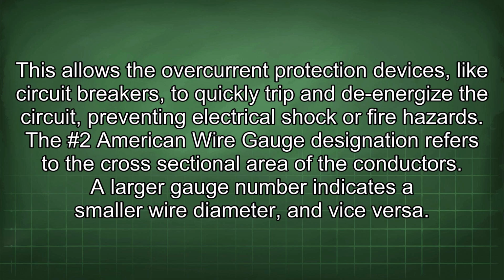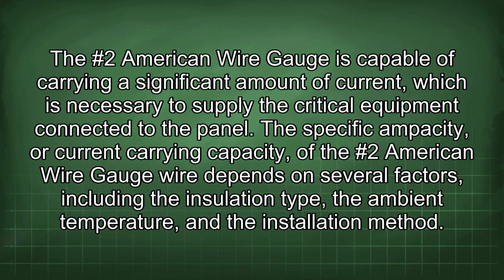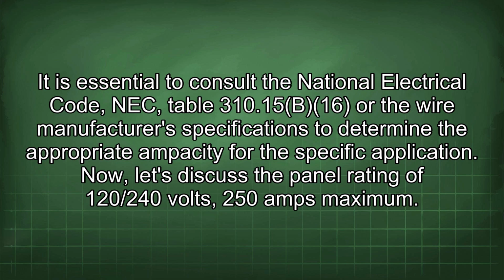The #2 American wire gauge designation refers to the cross-sectional area of the conductors. A larger gauge number indicates a smaller wire diameter, and vice versa. The #2 American wire gauge is capable of carrying a significant amount of current, which is necessary to supply the critical equipment connected to the panel. The specific ampacity, or current carrying capacity, of the #2 American wire gauge wire depends on several factors, including the insulation type, the ambient temperature, and the installation method. It is essential to consult the National Electrical Code, NEC Table 310.15(B)(16), or the wire manufacturer's specifications to determine the appropriate ampacity for the specific application.